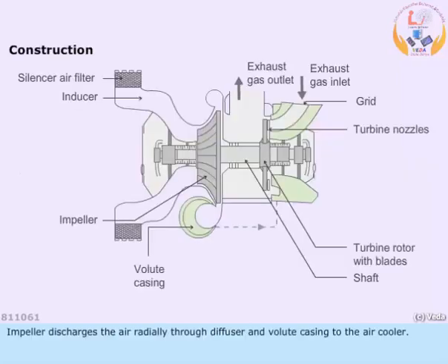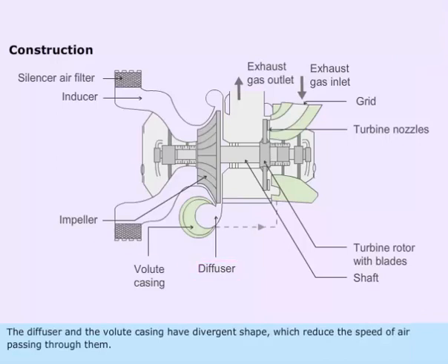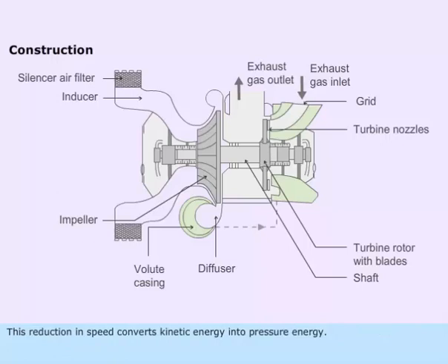The impeller discharges air radially through the diffuser and volute casing to the air cooler. The diffuser and volute casing have divergent shapes which reduce the speed of air passing through them. This reduction in speed converts kinetic energy into pressure energy.